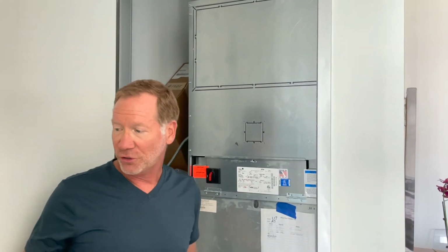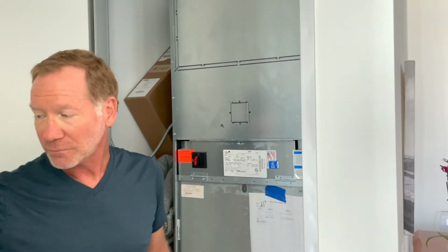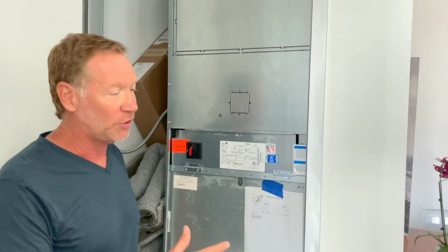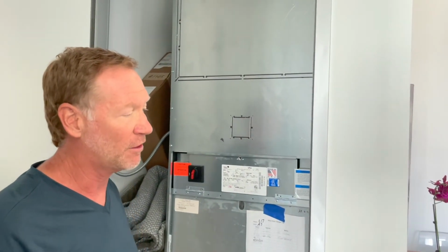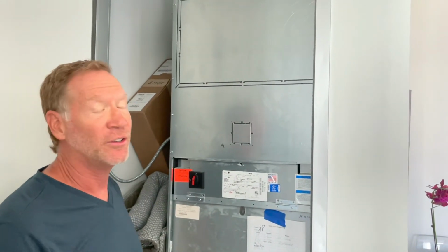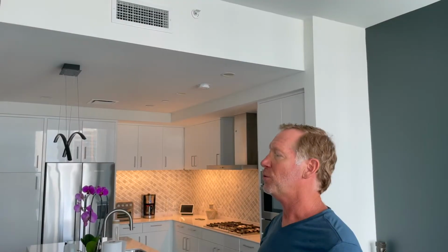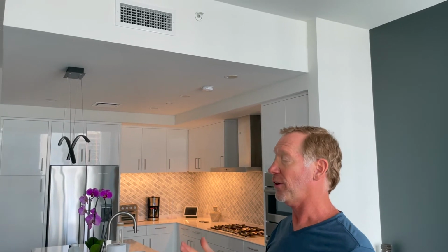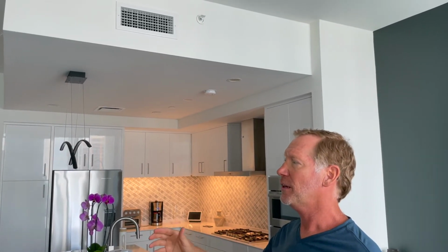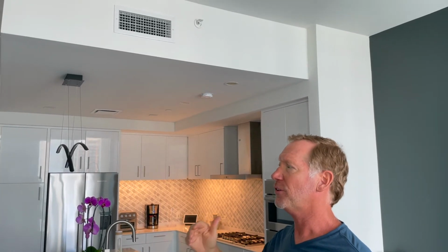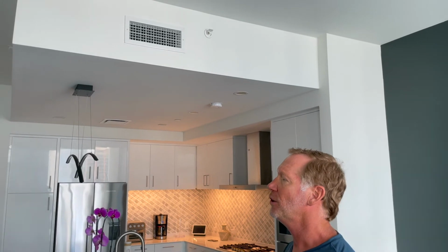So what we'll do is turn the AC on, let it run for a minute, and then I'll show you how to use a thermal thermometer to measure the temperature coming out of the vents. We talked about how the differential doesn't really make sense, at least not in my mind, because with these systems you should get a certain temperature of air, since the chilled water comes in at a certain temperature from the city.